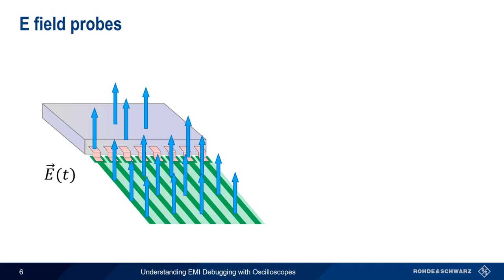E-field probes have their maximum response when placed parallel to the measured electric field. For most conductors, the E-field is perpendicular to the surface of the conductor, so we hold E-field probes perpendicular to the conductors we're testing.